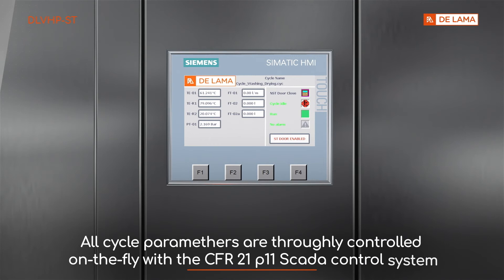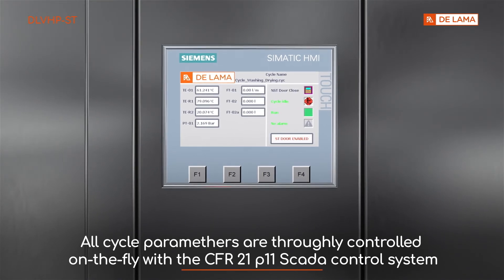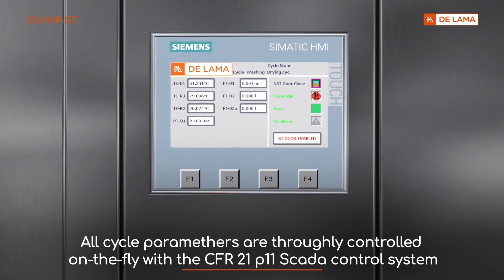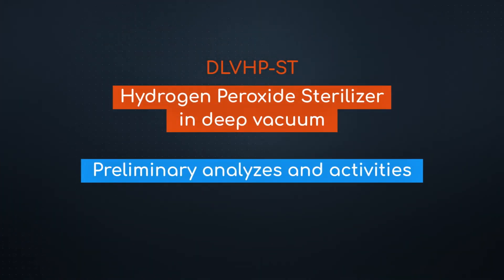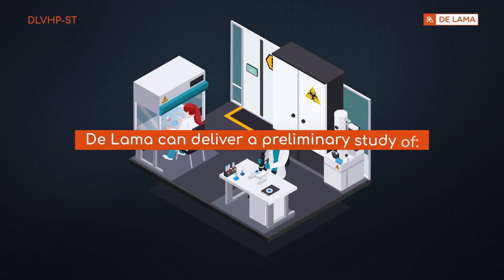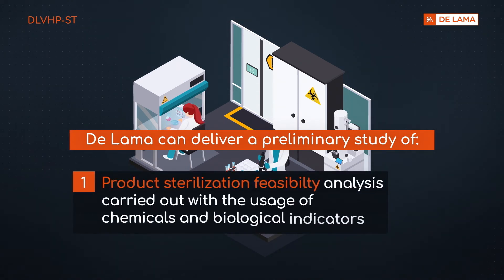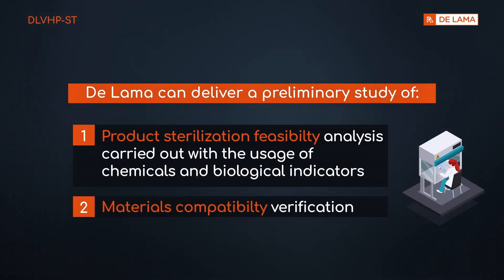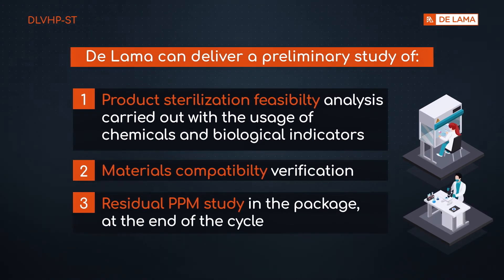All cycle parameters are thoroughly controlled on-the-fly with the CFR 21 Part 11 SCADA control system. De Lama can deliver a preliminary study of product sterilization feasibility analysis carried out with chemical and biological indicators, materials compatibility verification, and residual ppm study in the package at the end of the cycle.